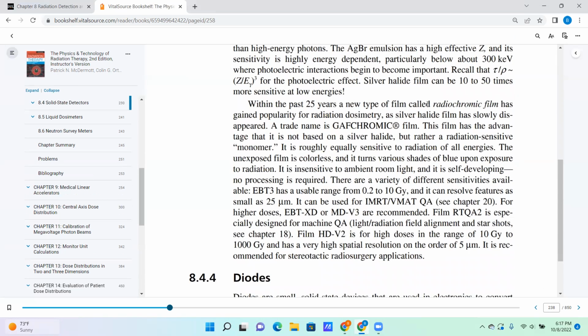In the past 25 years, a new type of film called radiochromic has gained popularity as silver halide film has slowly disappeared. A trade name is Gafchromic. This film has the advantage that it's not based on silver halide, but rather a radiation sensitive monomer. It's roughly equally sensitive to all energies.